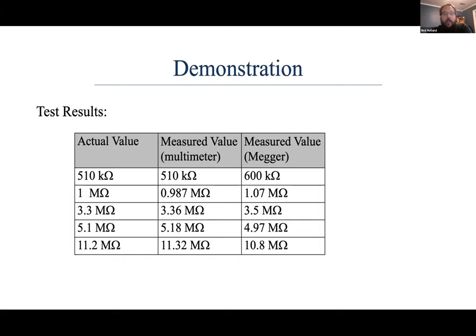That's very good. I was curious how much y'all got into it. This is a megohmmeter, which is actually used in the aviation world for airfield lighting quite a lot. They do insulation resistance tests, and there the FAA's minimum accepted value is 50 megaohms per circuit.